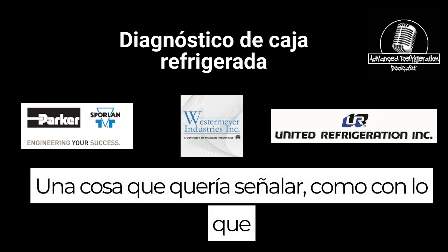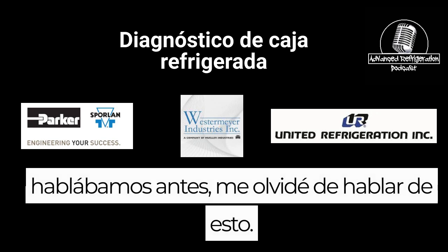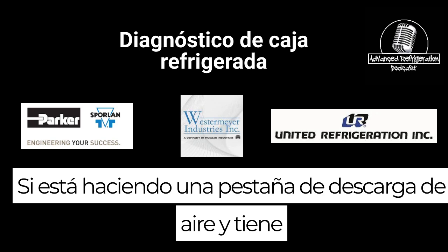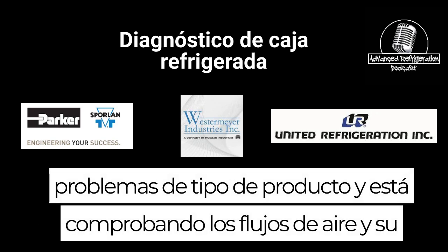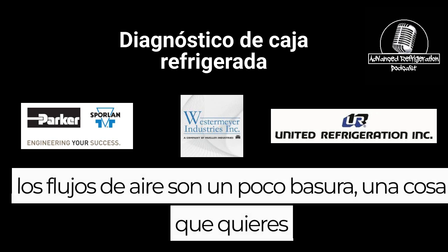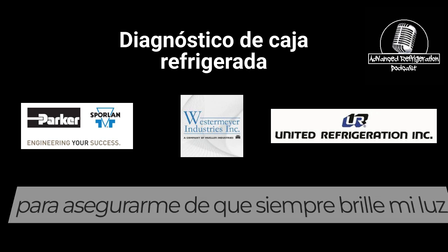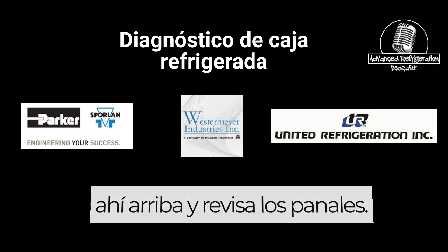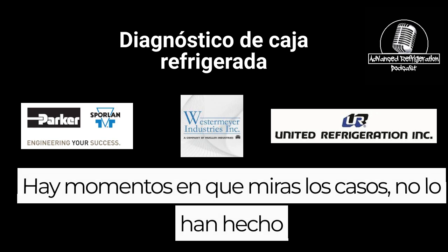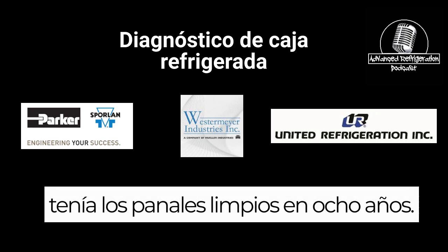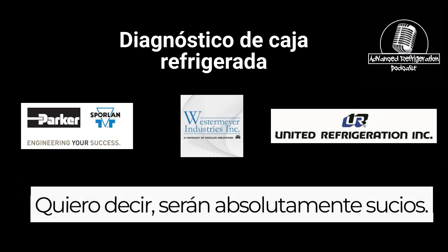One thing I wanted to point out, with what you were talking about earlier, I forgot to talk about this. If you're making discharge air temp and you're having product temp issues and you're checking airflows and your airflows are kind of crap, one thing you want to make sure of, I always shine my light out there and check the honeycombs. I mean, there's times you look at cases and they haven't had the honeycombs cleaned in 8 years. They will just be absolutely filthy.